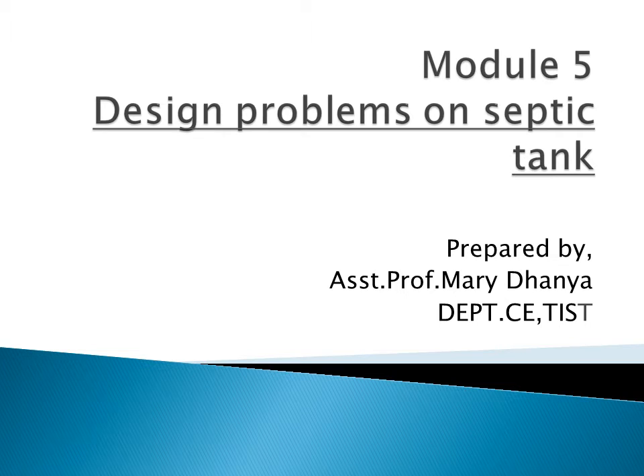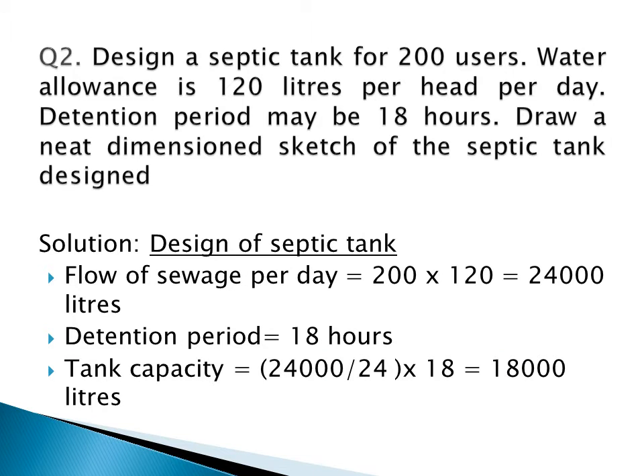Now let us start with the design problem of a septic tank. The question is to design a septic tank for 200 users. The water consumption is 120 liters per head per day. The detention period is given as 18 hours. You have to draw a neat dimensioned sketch of the septic tank after designing. First we will design the septic tank, then we will design the soak pit.